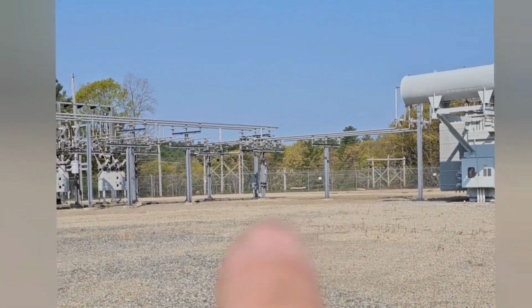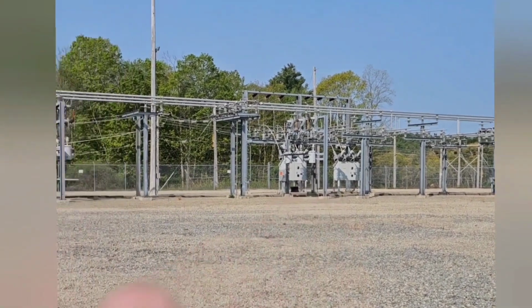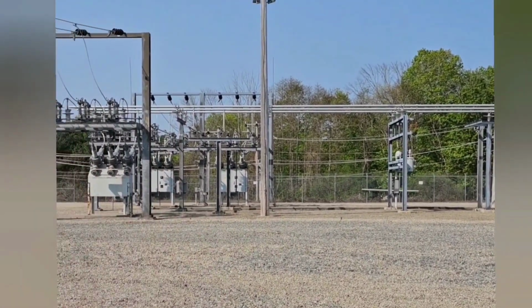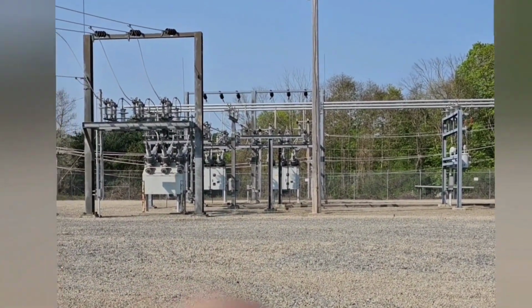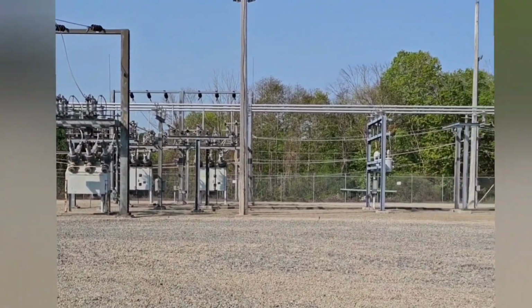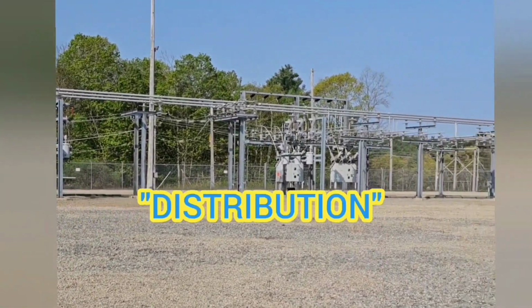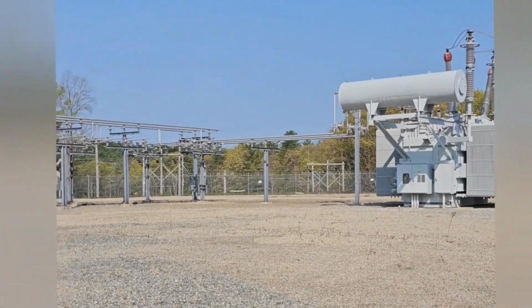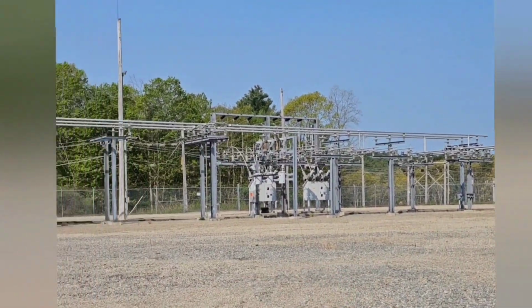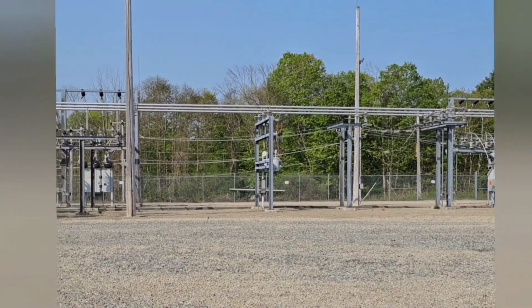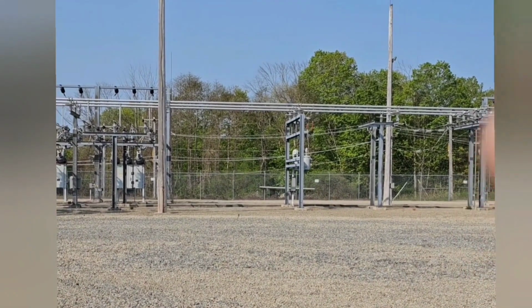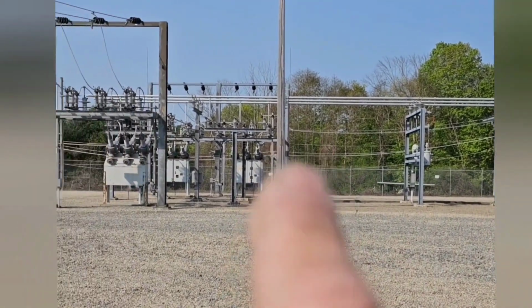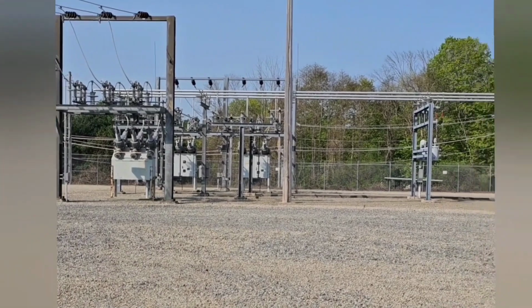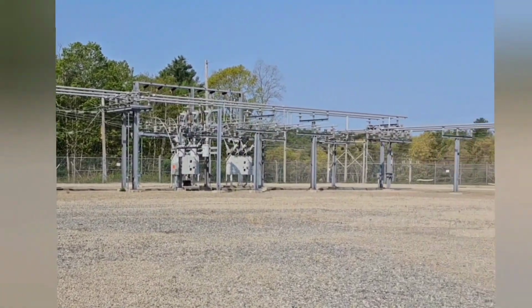That's on the low side, and then the power goes out to what we call a bus. There are 1, 2, 3, 4, 5 circuit breakers here where the power can be sent out to different areas, but the bus is energized from the transformer so that any one of these can open and close, and they'll still have power on the line side, which is what's feeding out to the different circuits that these go to, kind of like a circuit breaker in your house.